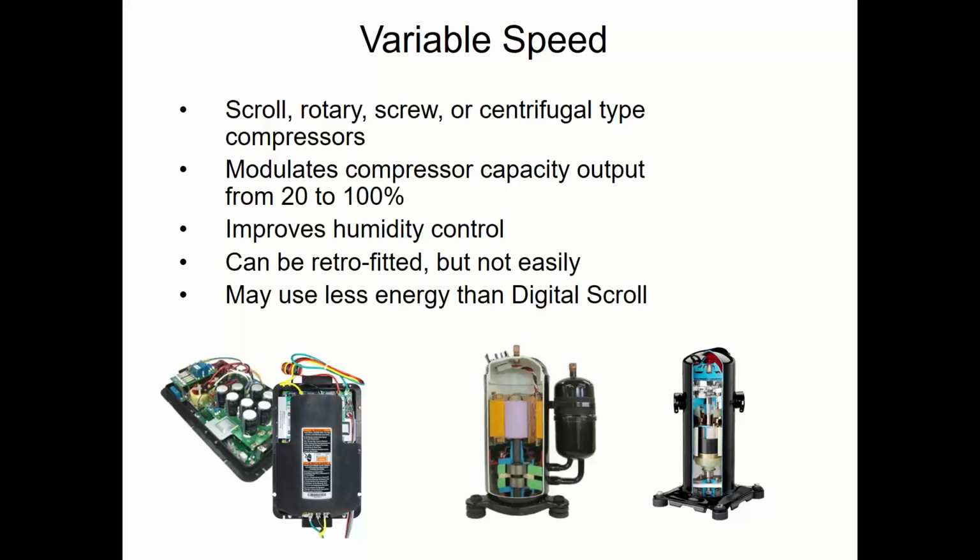But Carrier has a rooftop unit that has a variable speed compressor and a variable speed fan, and then it sequences those two things together to get tighter and tighter capacity control. Because of that, they also have to modulate the minimum damper position, so they can't use a standard economizer controller. They have to use more of a programmed one, right? Not a standard off-the-shelf Jade.